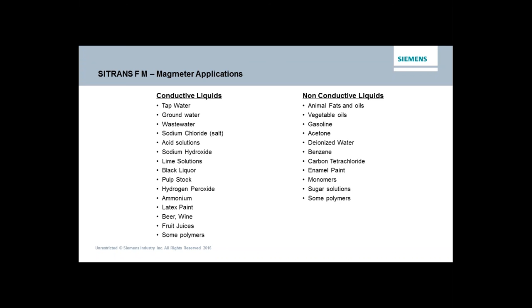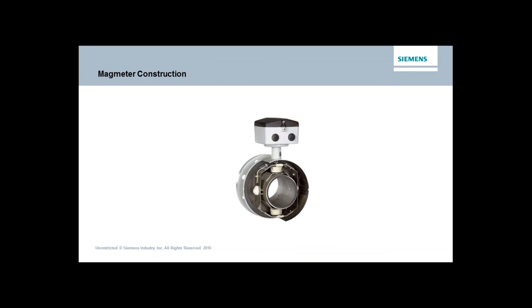If we look at a meter in a non-cross-sectional format, the first thing you've got is your process pipe. The flange on almost all mag meters is going to be made of carbon steel — it's epoxy-coated carbon steel. A lot of times I get requests from customers for stainless steel flanges. Regardless of who the manufacturer is, if you go to a stainless steel flange, two things are going to happen: your price is going to jump up significantly and your delivery is usually going to get pushed out significantly. The reason most manufacturers don't stock stainless steel flange meters is because the flange itself is not process wetted.